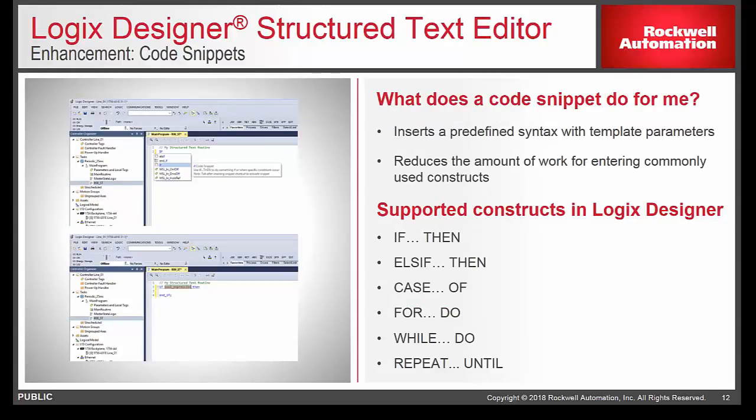One of the neat enhancements to V31 is the ability to implement code snippets inside structured text. Code snippets are predefined templates of code that are centered around constructs in Logix Designer. Code snippets essentially auto-insert predefined syntax that supports commonly used constructs in Logix Designer. Some of those are, as you can see here, if-then, else-if-then, case of, for do, while do, and repeat until.